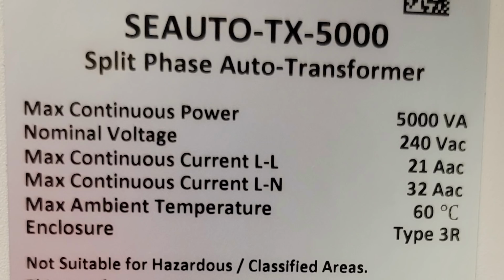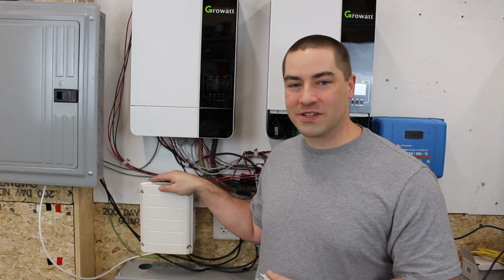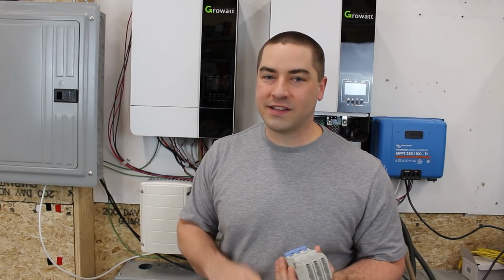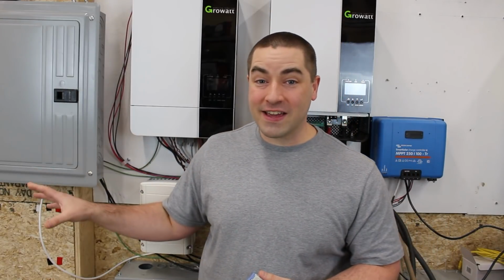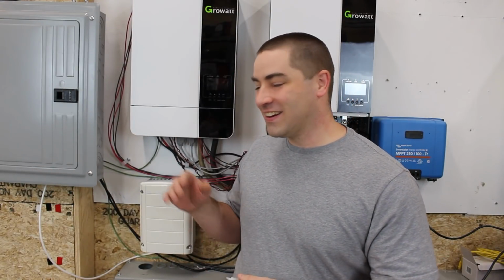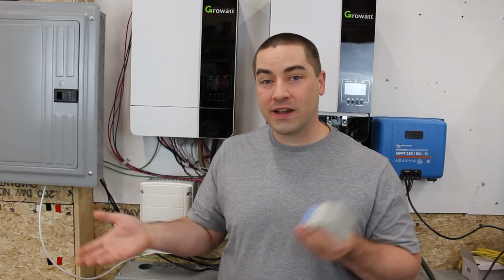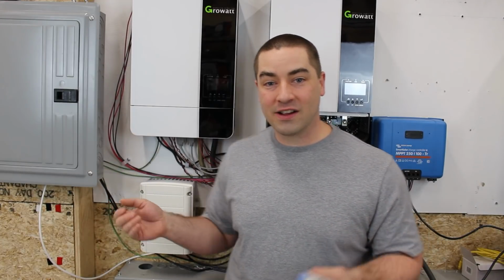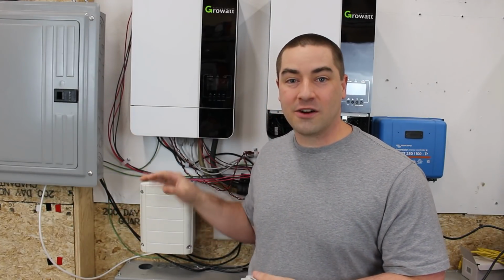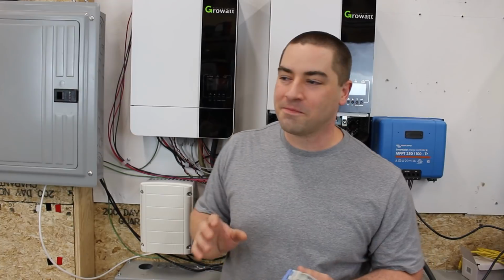Now this breaker is a 32 amp circuit breaker, and the auto transformer says continuous load on the neutral is 32 amps. So in order to overload this auto transformer, I'd have to be pulling a continuous load on a single phase without any load on the other phase. And the reason is because if you load down both phases, they balance each other out and they don't overload the auto transformer. They don't even go through the auto transformer.